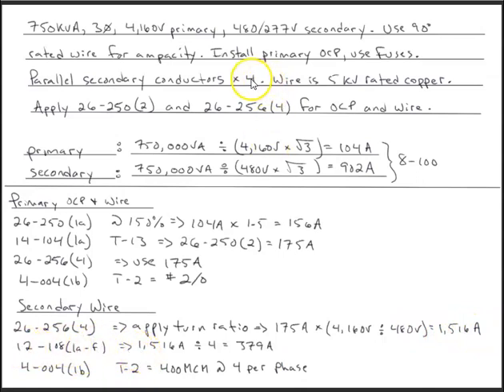Because we are paralleling times 4, we're going to divide this number by 4. That's 379 amps, and that represents one of the 400 MCM conductors. And then for table 2, we're going to find that 400 MCM covers the 379 amps, and there will be 4 of those for every phase. So 400 MCMs for A, B, and C phase, and the neutral should it apply. And that is it for transformers over 750 volts. We'll see you in the next episode.